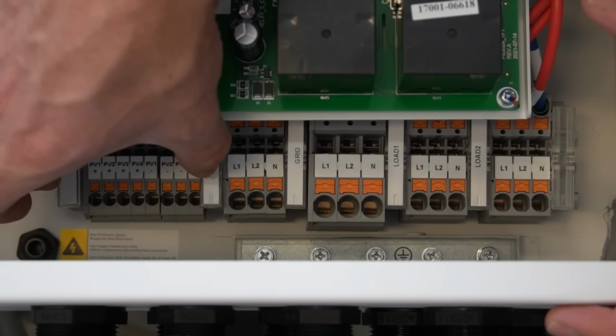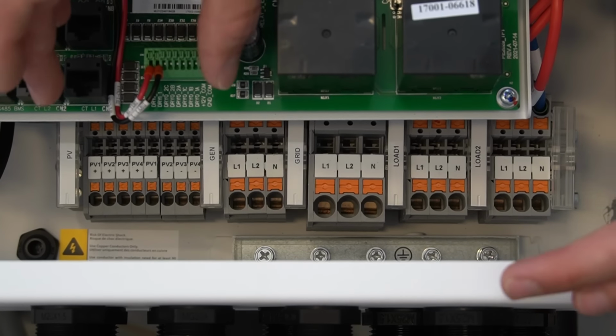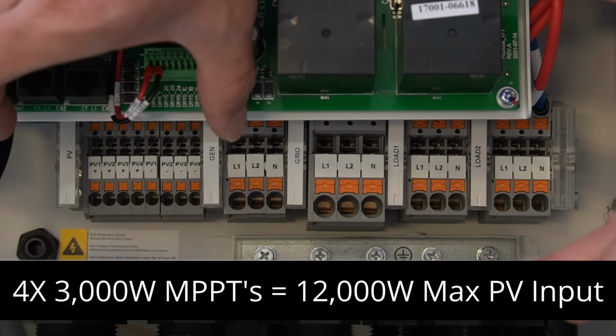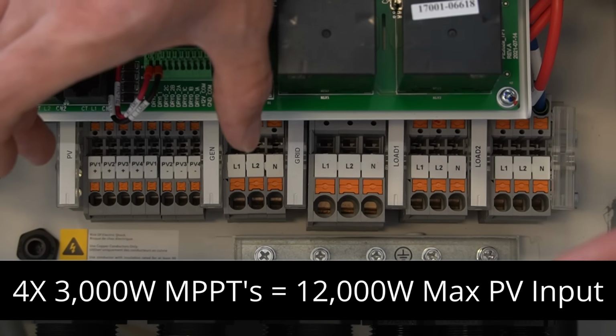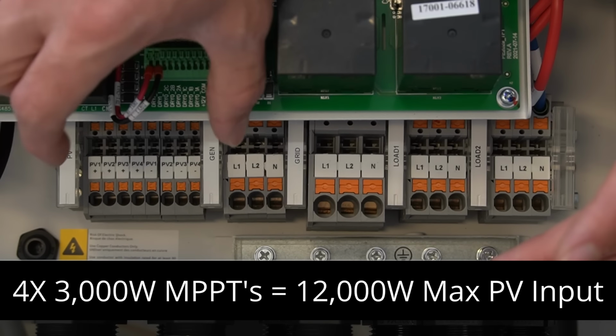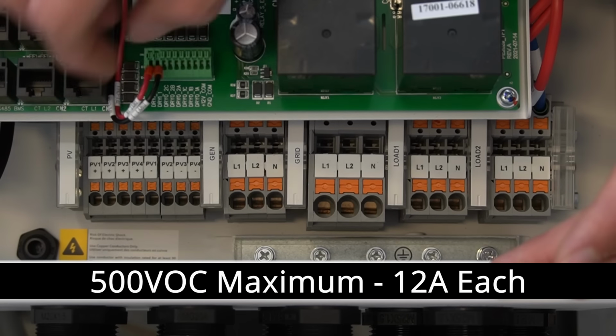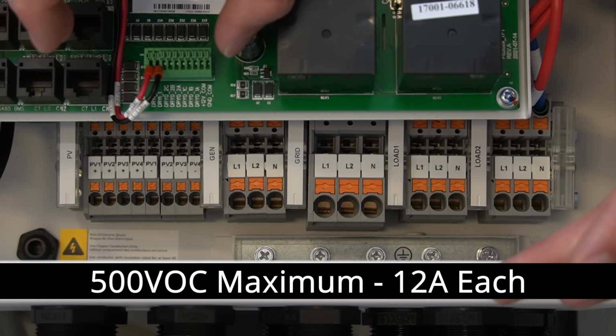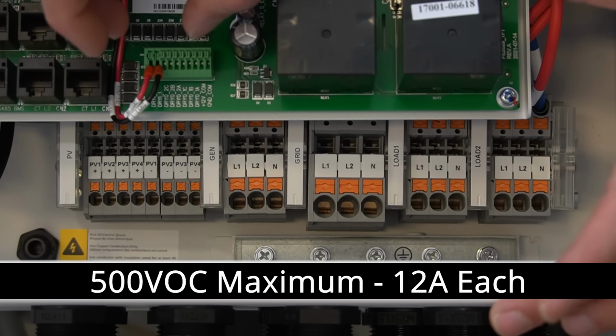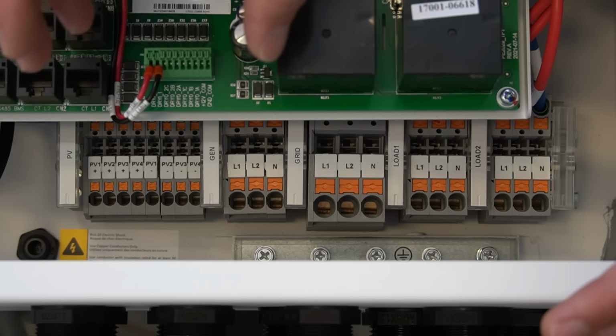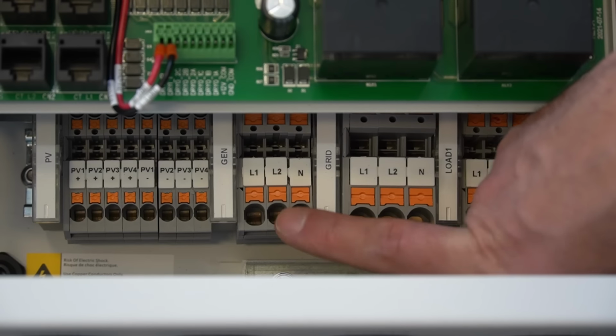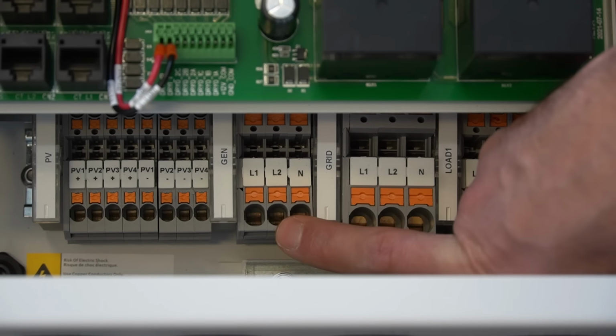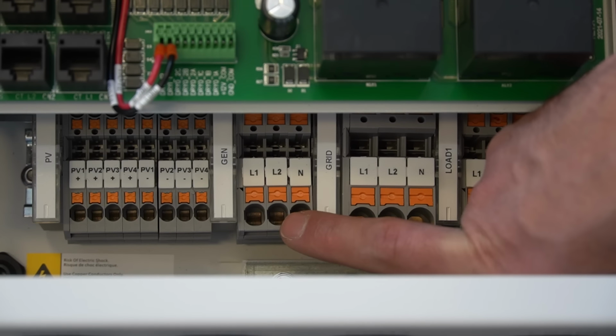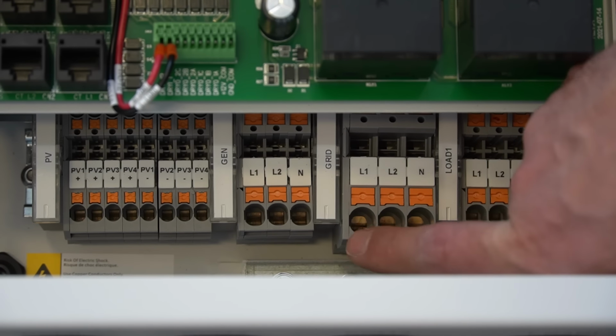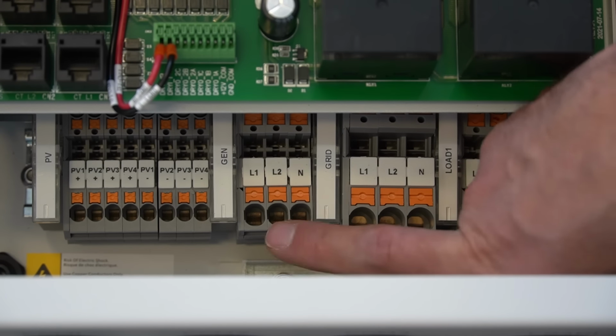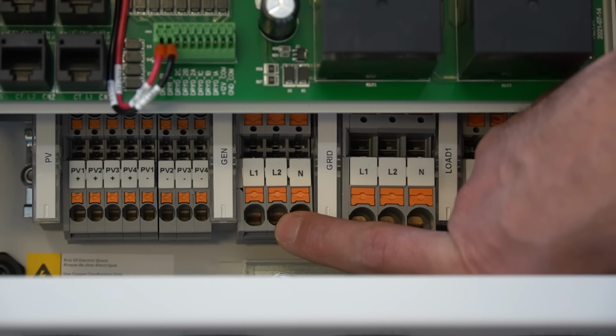So first on the left, the PV input is actually 4 MPPT solar charge controllers in one. You can connect a maximum of 12,000 watts to these terminals, and each terminal can handle 500 volts and a max current of 12 amps. So each input can handle its own single series string. Next, the generator connection can only handle 10 gauge wire, and that's because it doesn't have the same grid interactive features as this input. So the generator input is only for the AC charger.